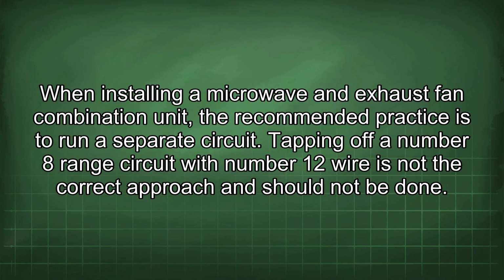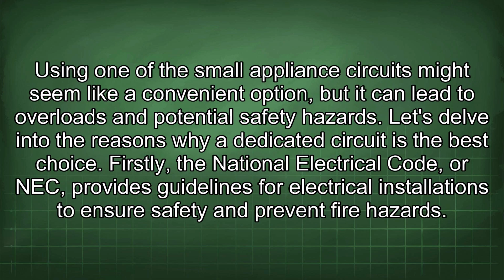When installing a microwave and exhaust fan combination unit, the recommended practice is to run a separate circuit. Tapping off a number 8 range circuit with number 12 wire is not the correct approach and should not be done. Using one of the small appliance circuits might seem like a convenient option, but it can lead to overloads and potential safety hazards. Let's delve into the reasons why a dedicated circuit is the best choice.